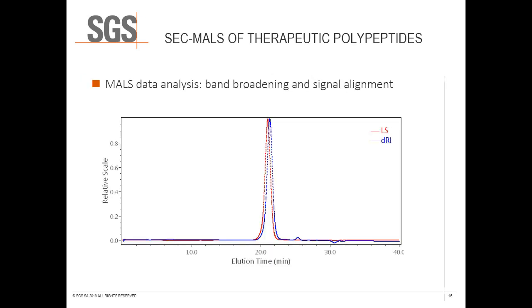For multi-angle light scattering, it is necessary, in addition to sample injections, to run a narrow molar mass distribution standard to align the detector signals by correcting for interdetector delay. Wyatt's Astra software also has a feature allowing for the correction of the sample band broadening as it travels between detectors. As you can see, the red-colored light scattering signal and blue refractive index signals are here misaligned, and the refractive index peak is very slightly broader than the light scattering peak.